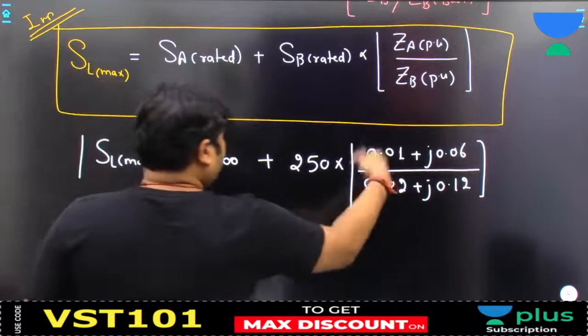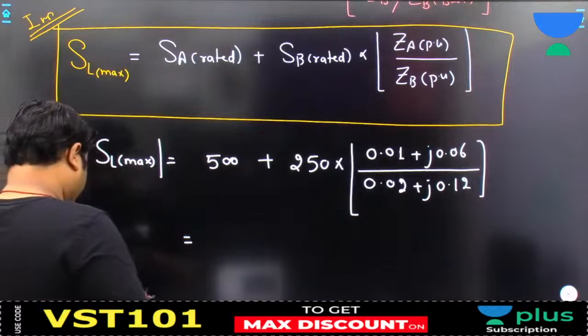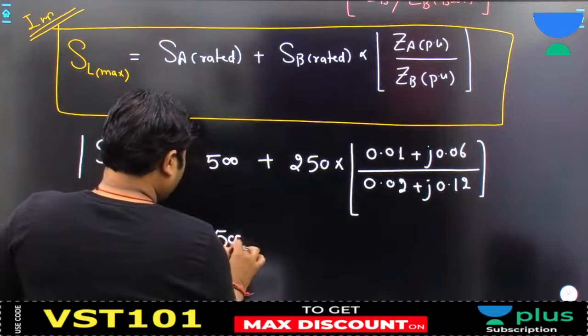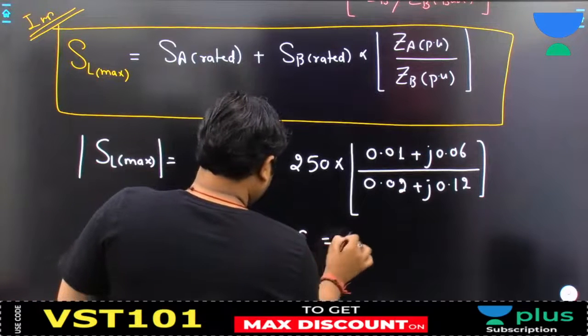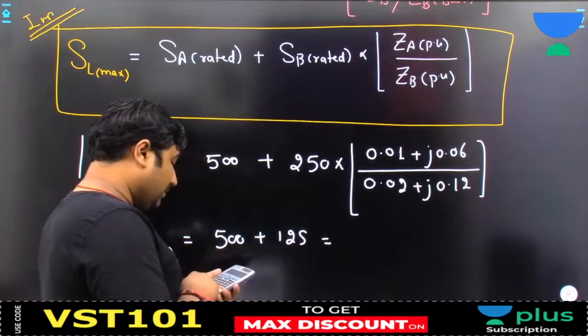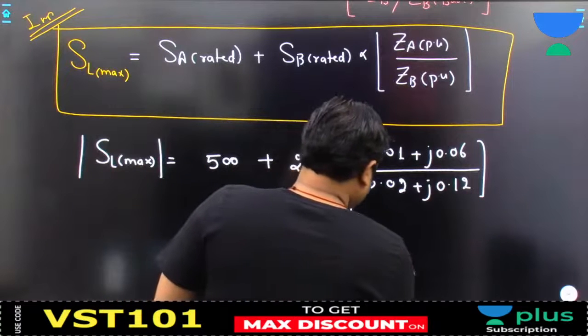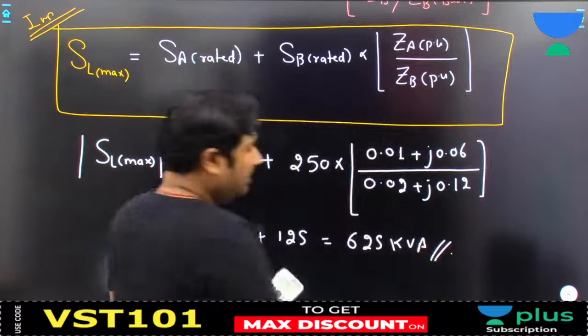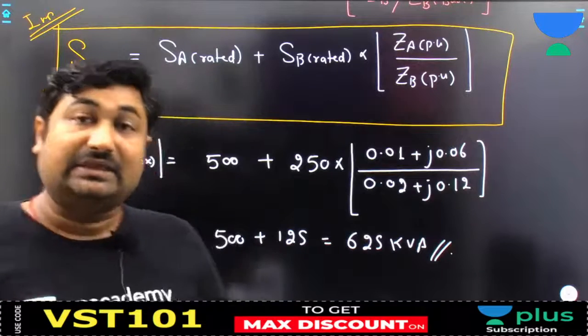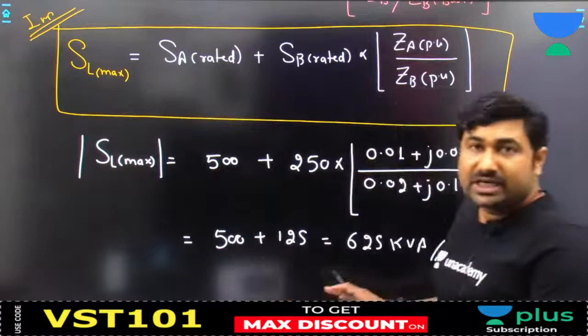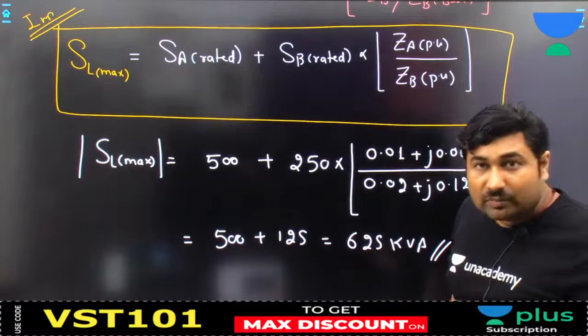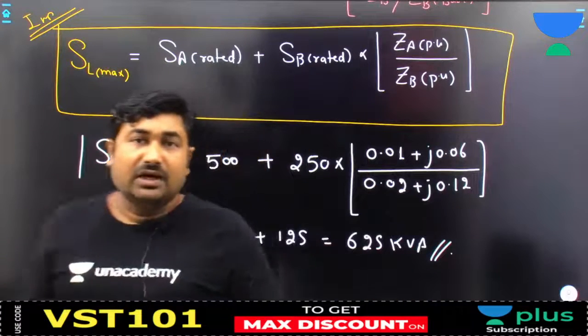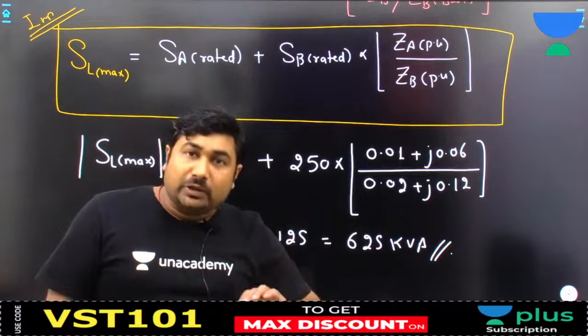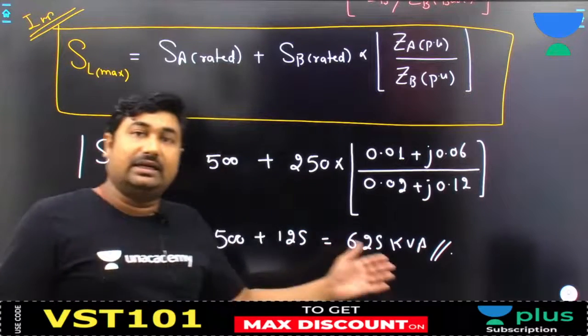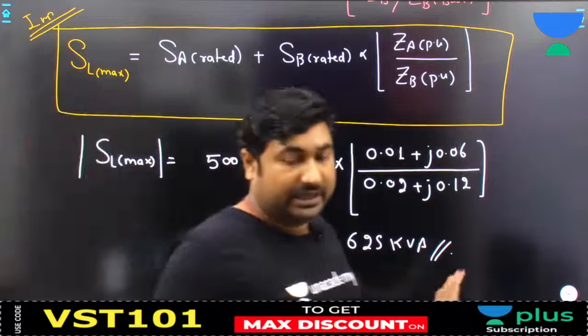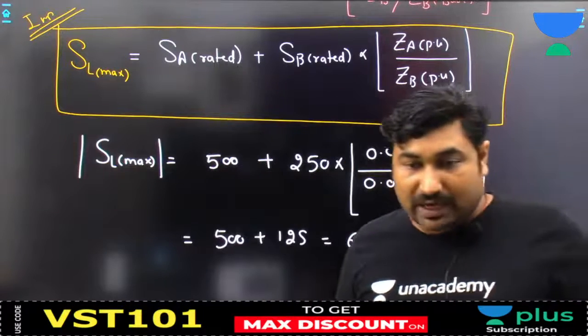So we are getting this to be 0.5 into 250, 125. So 500 plus 125. It means the maximum kVA that this combination can handle is equal to 625 kVA. By observing the rating plates, we think that they are going to share the load of 750 kVA, but no, they can maximum share a load of 625 kVA. If you increase the load beyond this, then transformer A is going to be overloaded. Are we able to understand up to this part?